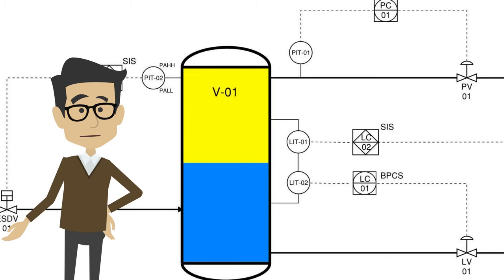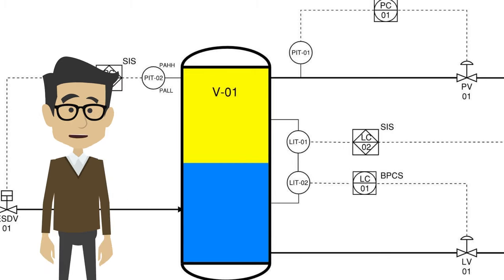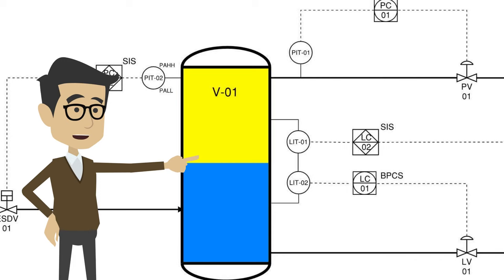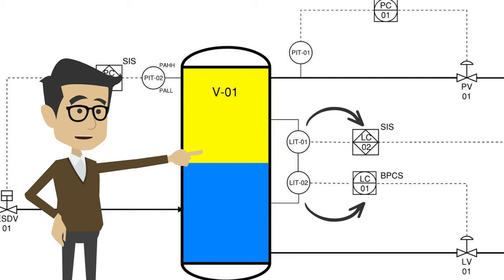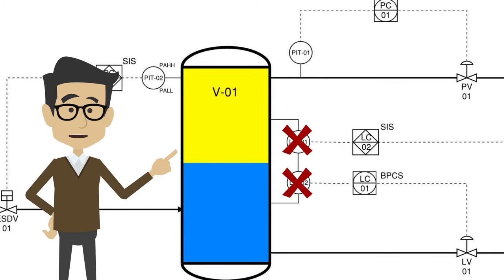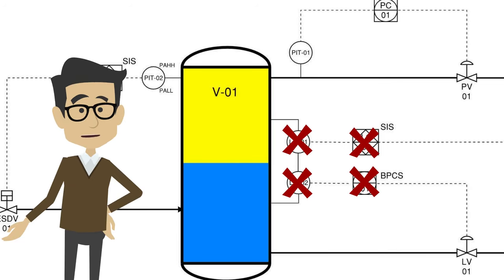To do this effectively, the SIS cannot share any potential common cause failures with the BPCS that would jeopardize its ability to act. An example of this would be using the same level bridle in a vessel for both the BPCS and SIS transmitters. If the bridle is plugged, control of both systems would fail.